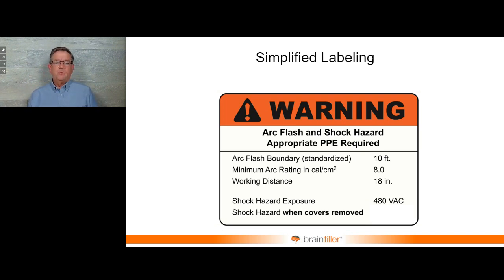And then have an arc rating of the PPE. Forget about the calculations. You still need those to be documented, but just put the PPE arc rating and then the voltage on there. And what's so great about this is, if you go back and review the study at periodic intervals, and numbers go up or down, like it goes from 5.3 calories to 5.8 calories, so what? 8 calorie PPE still works. Your boundary goes up or down a little bit, so what? If it's still within 10 feet, still good. You don't have to relabel. And you can put a little maintenance sticker like I show here in the lower right, that just says, hey, we reviewed this, still good to go.